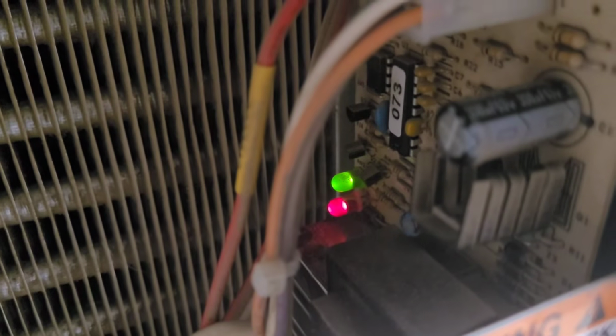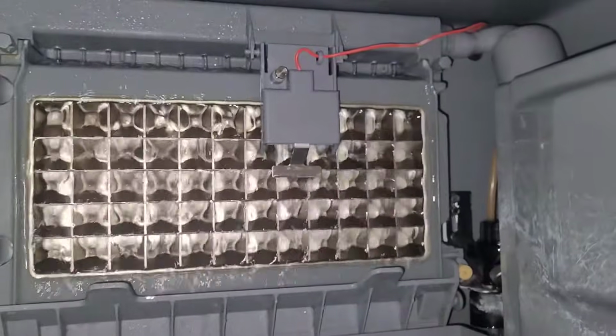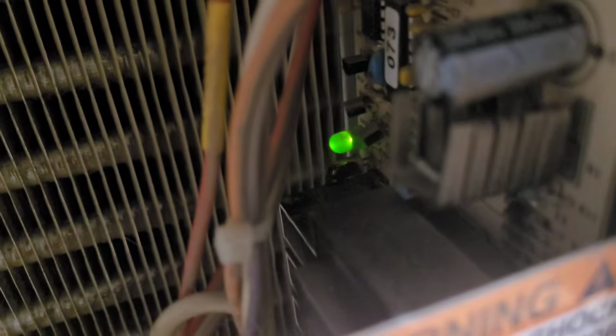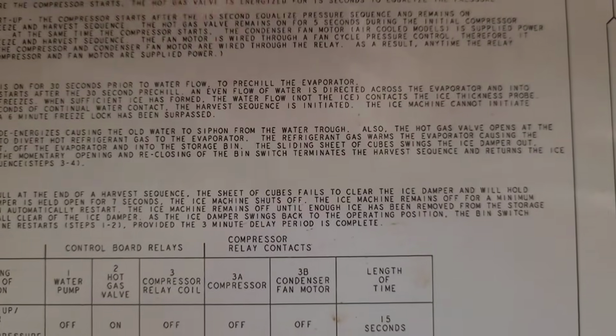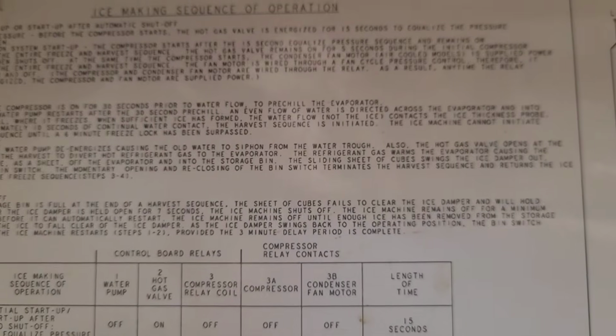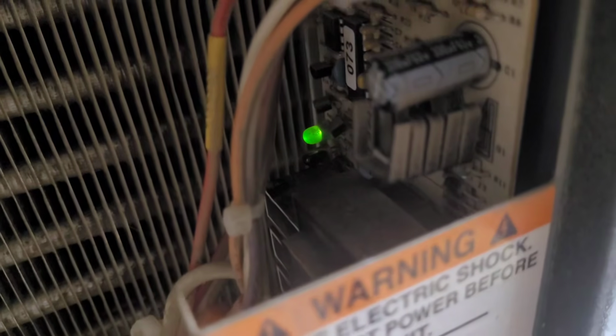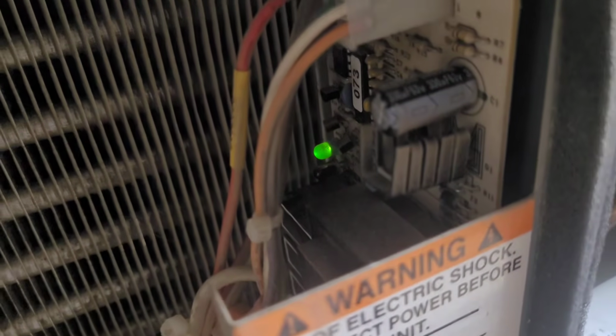We're starting to get some intermittent water contact. We're getting close. So the water flow, not the ice contact, contacts the ice thickness probe. After approximately 10 seconds of continual water contact, the harvest sequence is initiated. The ice machine cannot initiate a harvest sequence until a 6-minute freeze lock has been surpassed. So once we get 10 seconds of that light on, it'll switch, which we're getting really close to.